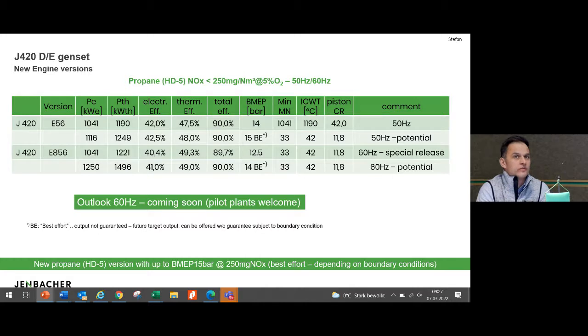Also, an improvement with the new engine we see on the propane versions. Based on HD5, we can guarantee now 14 bar BMEP. This means 1 megawatt electrical output on 50 Hz, and we have a potential there to increase the power output even further to 15 bar, but this is for sure depending on the site conditions, on the fuel, and currently we cannot sell it, but it's a subject to the boundary conditions on site.